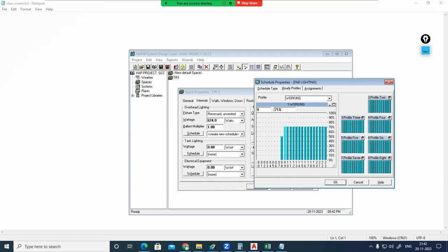Then 9 a.m. to 17. 17 means 5 p.m. Everyone will be using the light fitting. I'm just considering 100%, but at the same time, 1 second, 9 a.m. to like 12, I'll be considering 100. Okay. Then 13 to 14, lunch time, you can provide that as 50. Means lunch time, people might not be using that much light fitting, say 50%. But lunch time also you want to consider, even that also you can consider. Okay. Now, 15 to 17, that will be 100%, fine.